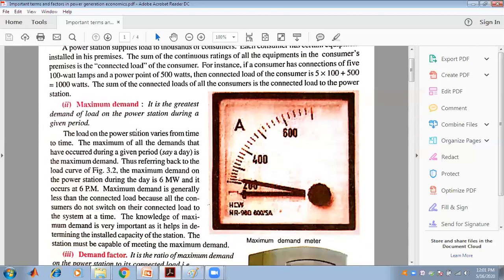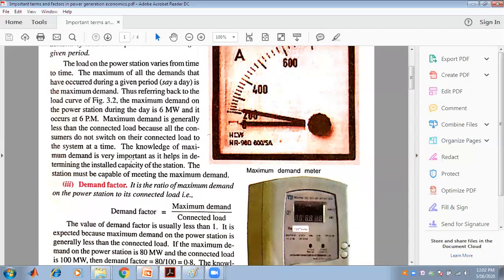The second factor is the maximum demand. It is the greatest demand of the load on the power station. From the load curve, different types of demands are present, and the highest among them gives the maximum demand. The knowledge of maximum demand is very important as it helps determine the installed capacity of the station. The station must be capable of meeting the maximum demand.